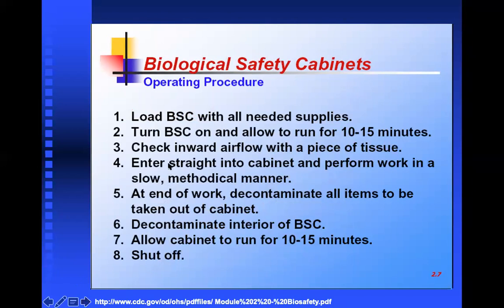Operating procedure: load the biosafety cabinet with all needed supplies the first time when you do the job, and turn the biosafety cabinet on and allow it to run for 10 to 15 minutes. You have to allow 10 to 15 minutes, and check inward airflow with a piece of tissue, enter straight into the cabinet and perform work in a slow, methodical manner. At the end of work, decontaminate all items to be taken out of the cabinet, and clean using ethanol. We clean the full cabinet and decontaminate the interior of the biosafety cabinet. Allow the cabinet to run for 10 to 15 minutes and shut the door. So this is the principle.